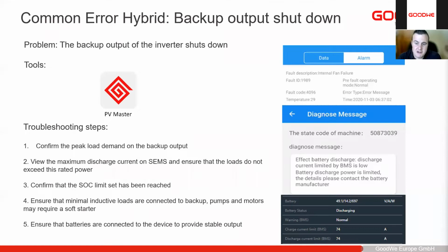View the maximum discharge current of our batteries. Very often the battery discharge current certainly does affect the maximum load you can run when you only have batteries available. The inverter won't take more from the batteries than what the BMS reports to it. An example of this is here below, where we can see only a 74 amp discharge. So on low voltage, you can see it's a 48 volt nominal system. 74 amps is only about 3.6 kilowatts. So although you may have a 4 kilowatt or 5 kilowatt inverter, when there's only batteries available, we will only be able to discharge that 3.6 kilowatts.